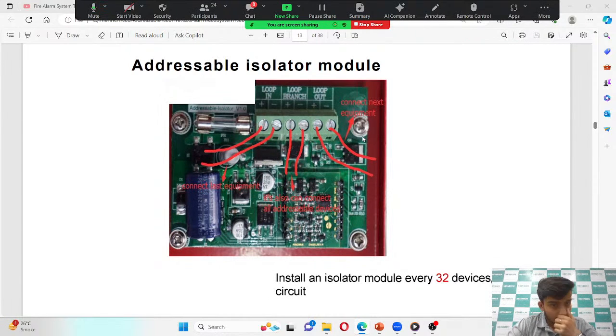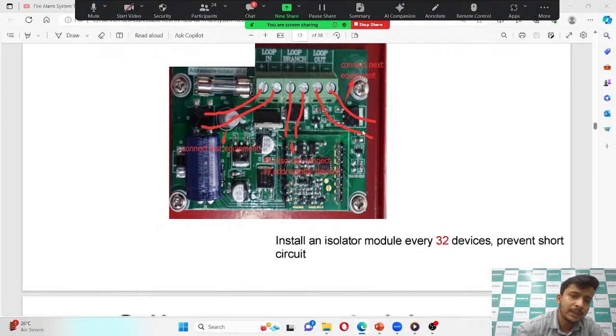Then the addressable isolator module. It also has 3 ports: loop in, loop branch, and loop out. So how will it be connected? The loop in port will be connected with the last device of the branch which you are adding from a main loop. The main loop will be connected at the loop branch port, and then loop out. From loop out, you need to take one more cable for the new loop, and then the last device of that new loop will be connected with the loop in port. As I already told you, the isolator module will be installed at every 32 devices in a loop.